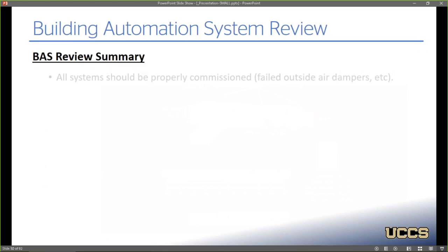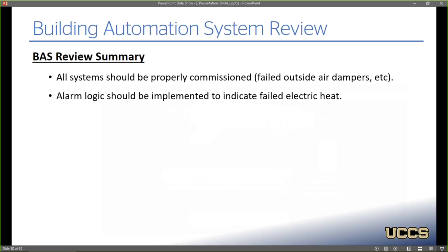So in summary, when looking at the BAS, I think it would be really important that all these systems be properly commissioned. They have these failed outside air dampers, failed electric heat. It was never commissioned in the first place, so there may be even other issues that would be made apparent during more detailed functional performance testing or point-to-point verification. Some alarm logic should be implemented to indicate failed electric heat. The customer had no idea that these reheats had failed.